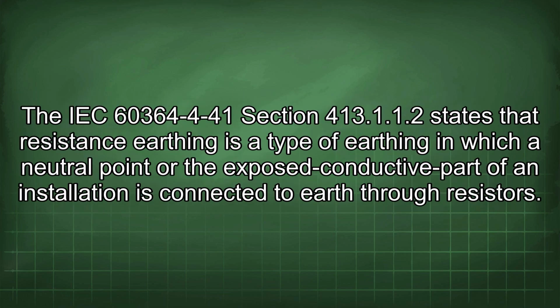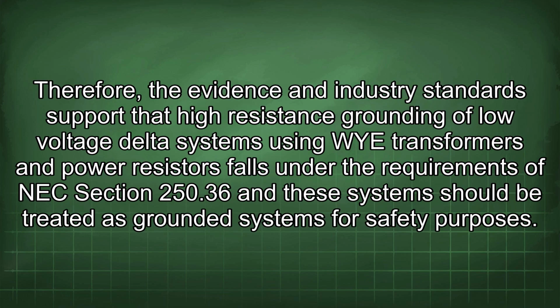The IEC 60364-4-41 Section 413.1.1.2 states that resistance earthing is a type of earthing in which a neutral point or the exposed conductive part of an installation is connected to earth through resistors. Therefore, the evidence and industry standards support that high resistance grounding of low voltage delta systems using WYE transformers and power resistors falls under the requirements of NEC section 250.36, and these systems should be treated as grounded systems for safety purposes.